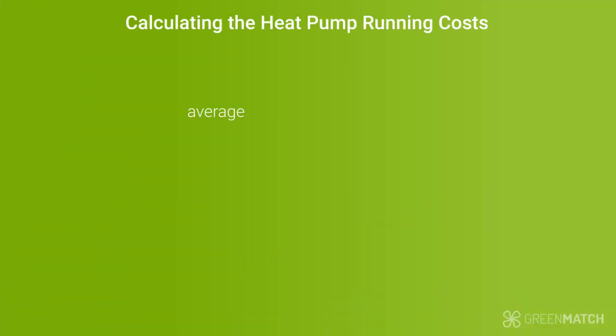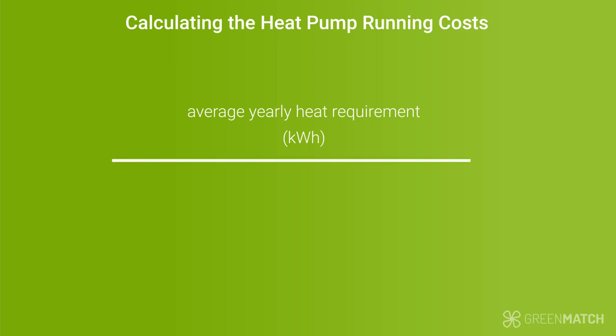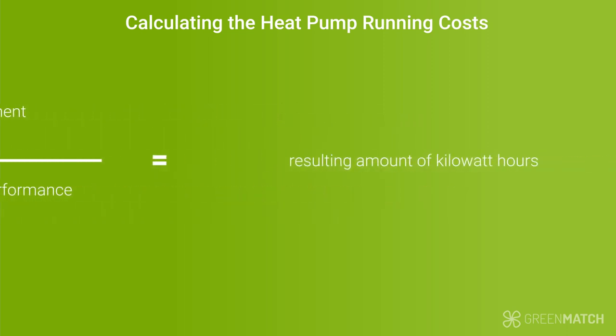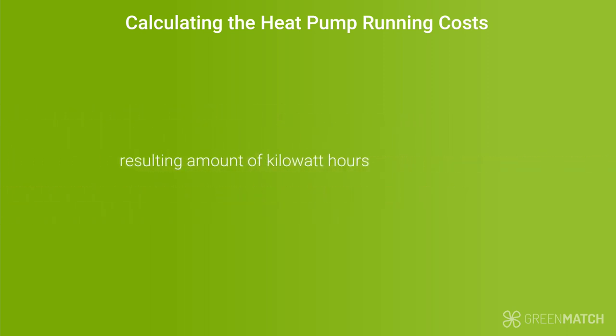Take the average yearly heat requirement of the property in kilowatt hours. Divide the average yearly heat requirement by the heat pump's seasonal coefficient of performance. Take the resulting amount of kilowatt hours and multiply them by 18.9p — the average cost per kilowatt hour of electricity in 2021, according to Ofgem.